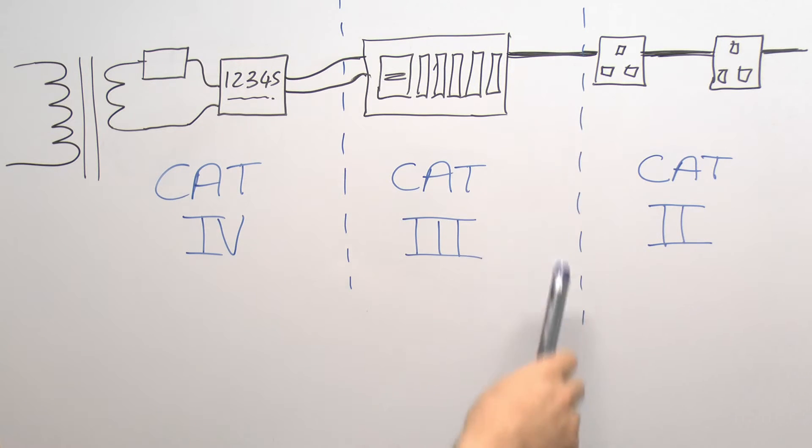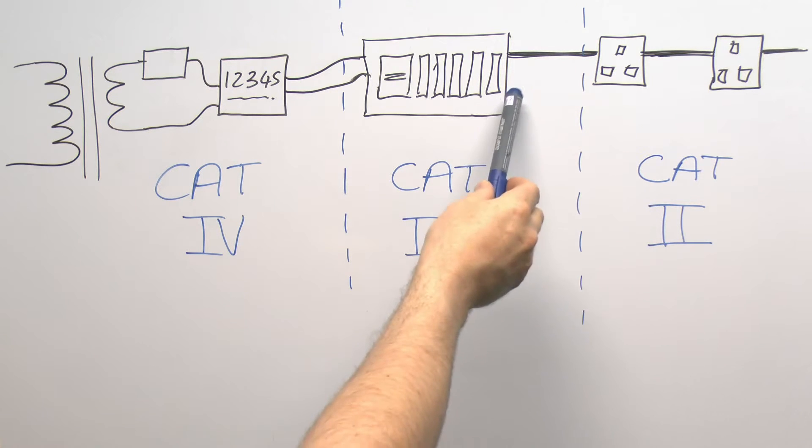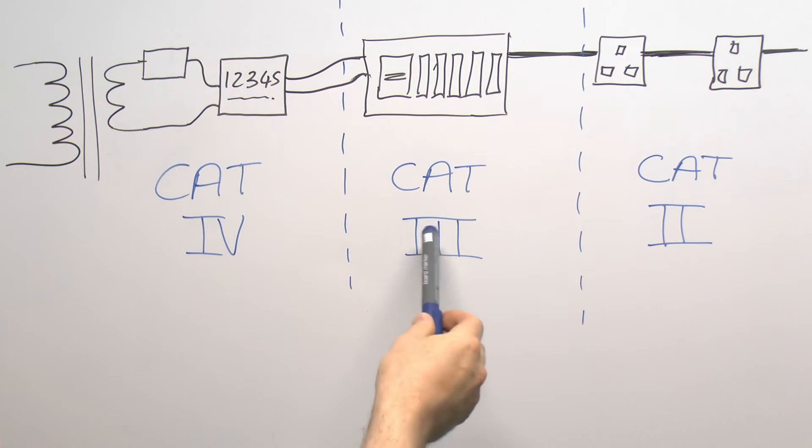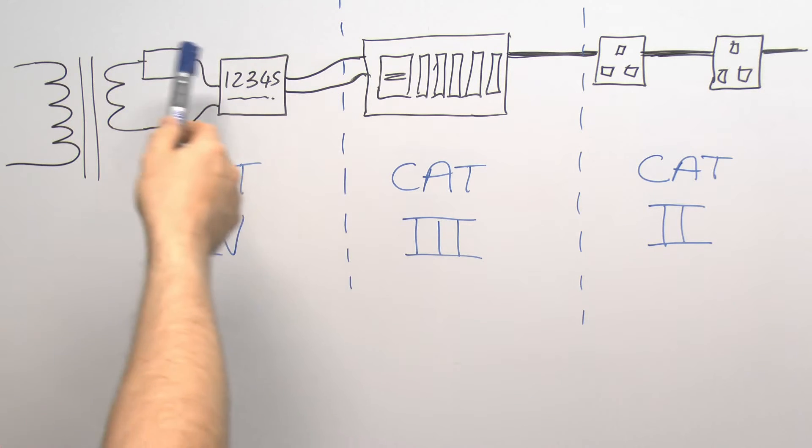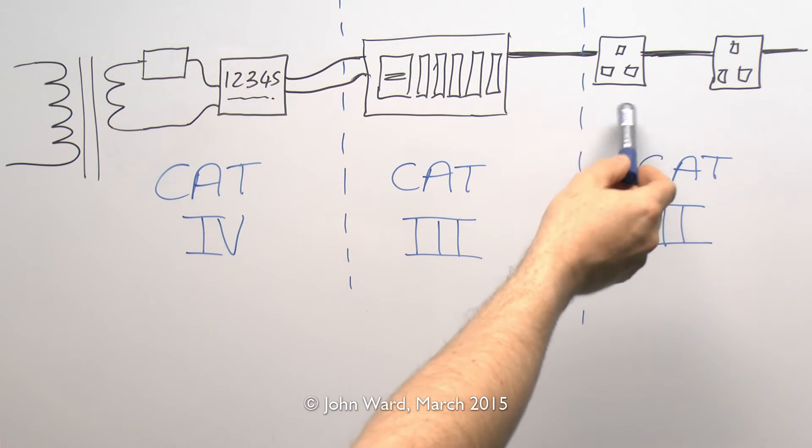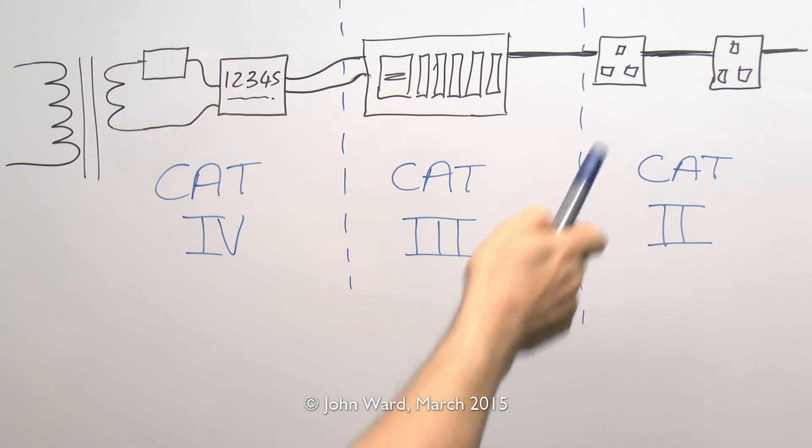These boundaries note aren't specifically defined like this because for example a socket outlet right at the distribution board will still be a category 3 situation. So it all depends on the actual distance away that you're going. And again if you poked about the consumer unit and managed to short out the incoming terminals there well that's probably going to be a category 4 because again you're only moving into this section here. So although I've put the lines there those are not set in stone as it were. They're just general guidelines as to the distance you're moving away from the source. And generally the more protective devices you have as you move further away. And certainly in the UK if you were going to plug an item in here it would obviously have a fuse in the plug. So again you've got fuse here, circuit breakers and again the main incoming fuse as well.